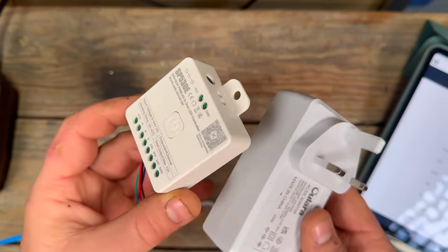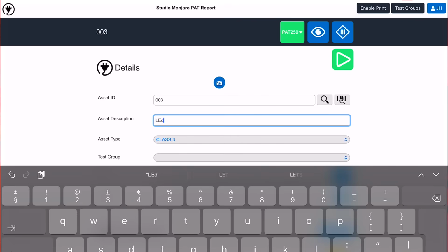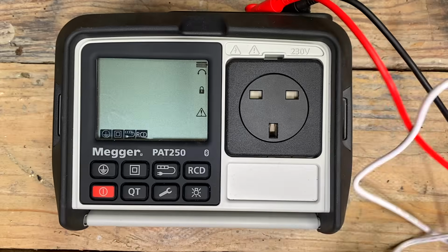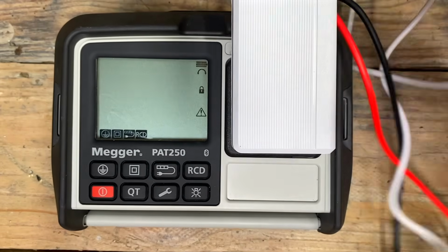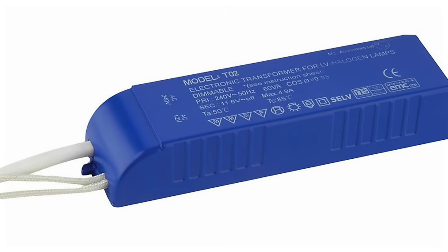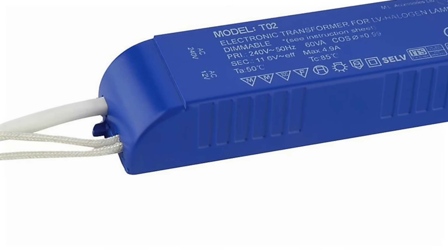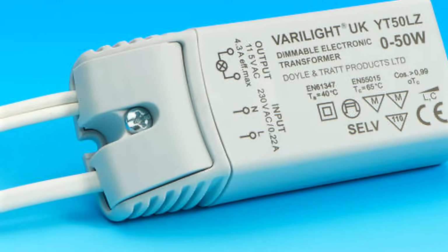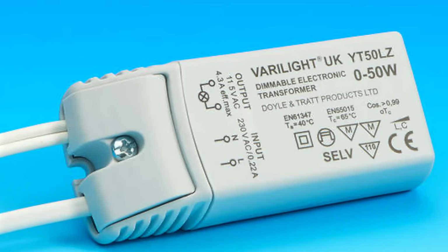But I have an LED driver here that operates at 24 volts and outputs at 24 volts. The only real test I can do here is confirm the voltage, and that's about it. A lot of other transformers don't have an earth connection on the secondary side, so I can't really confirm that the protective conductor is separate. But we log that in the record and make notes as needed.